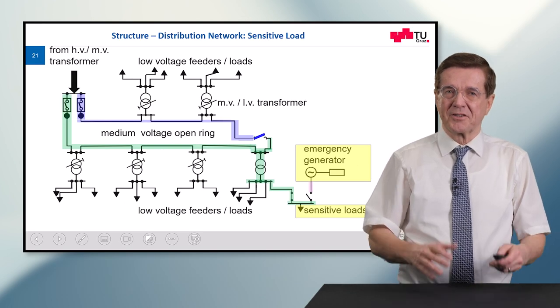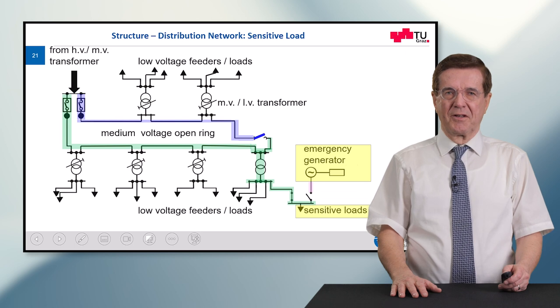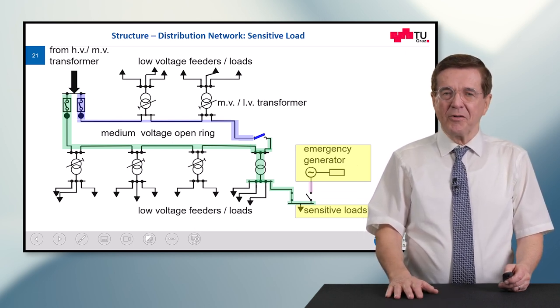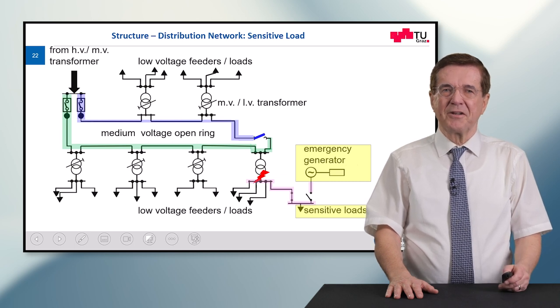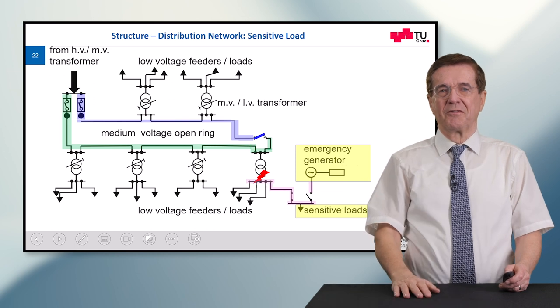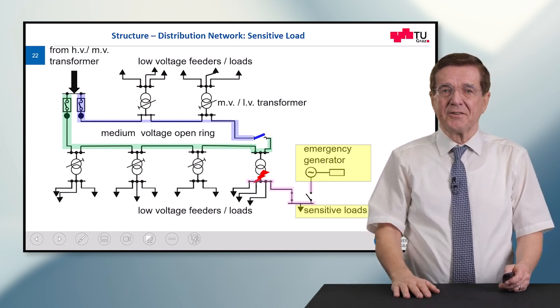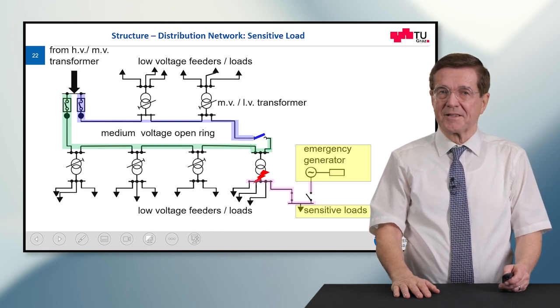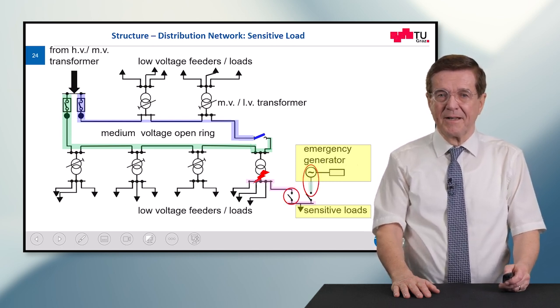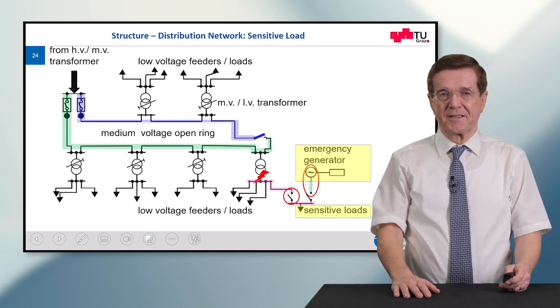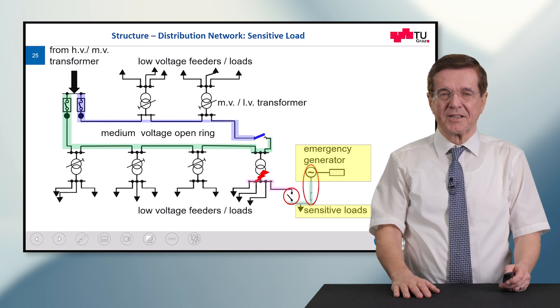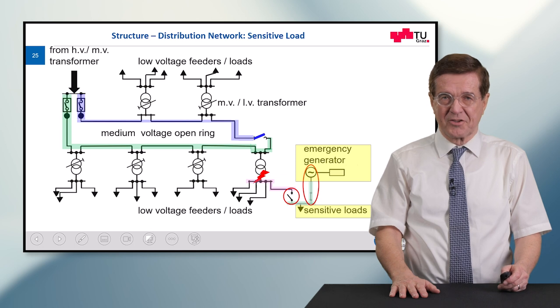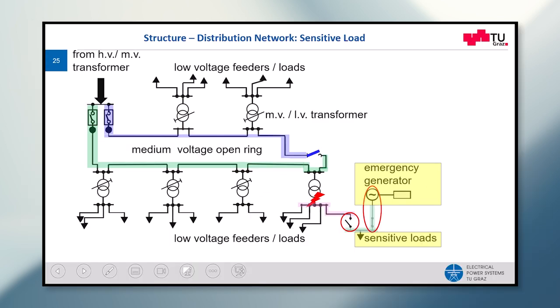In addition to this quite safe supply, you may have very sensitive loads — for example, a hospital. When a fault happens, a ring structure does not help because you cannot get energy to the lower voltage level, to the low voltage side. The sensitive loads are no longer supplied. At that very moment, an emergency generator is started up: the normal supply to the sensitive loads is interrupted and the emergency generator re-energizes them. So in a hospital, for example, the sensitive loads are supplied with only a very short interruption, while the rest unfortunately has to wait until repair work has been done.